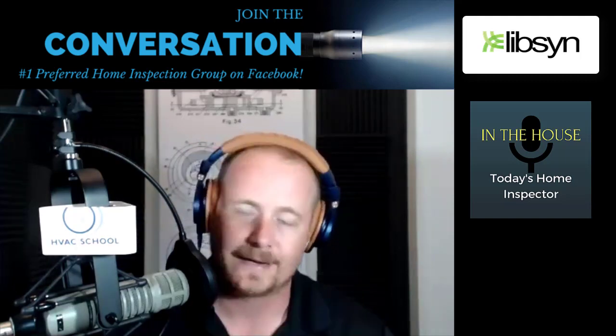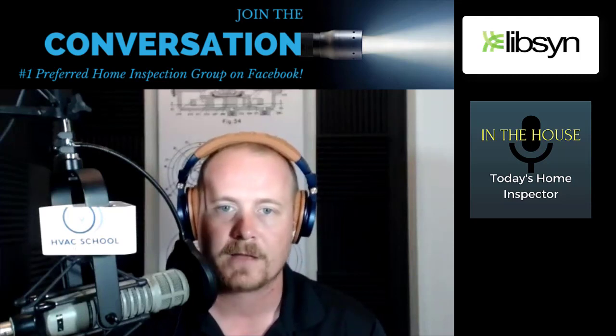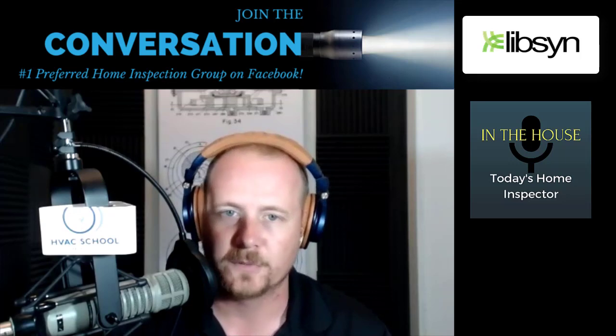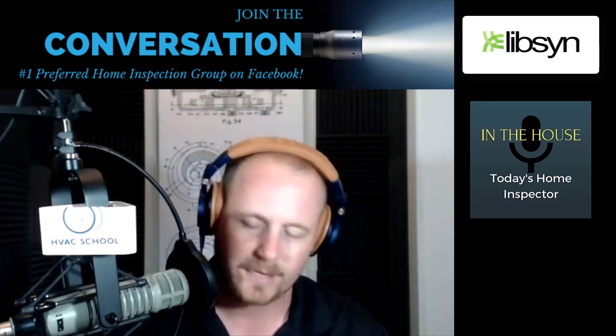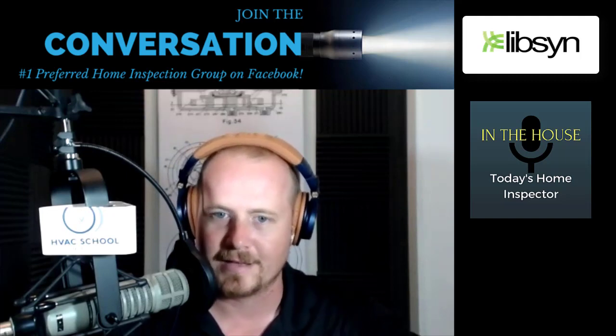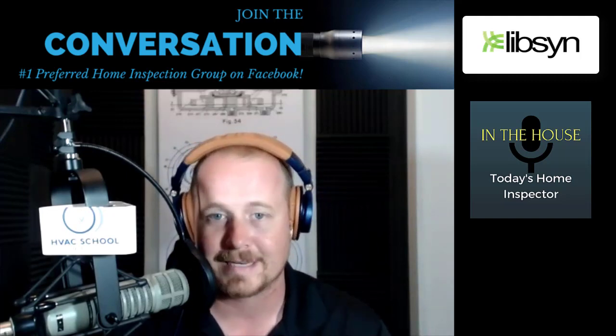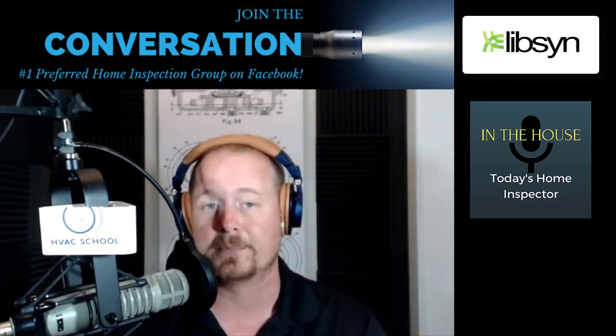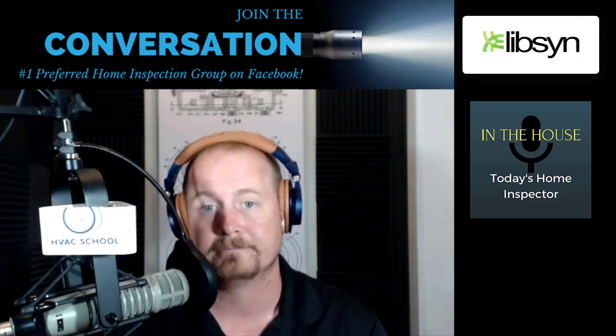Because I can't tell you how many times I've seen reports that say, I've seen hundreds of these, system's running a 14-degree split, needs to be looked at. Well, they're taking a 14-degree split at the diffuser in the house, at the vent, and then they're taking it at the return. And that's actually very, very common. And in fact, you will have a 14-degree split as a matter of course, even at the unit, if the indoor temperatures and indoor relative humidities are high.